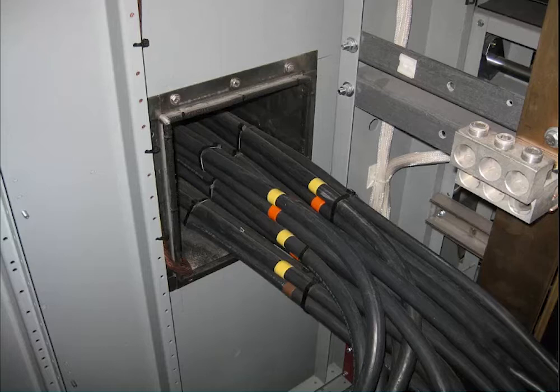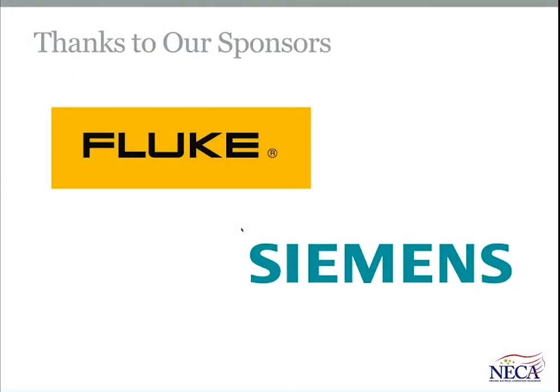And as soon as you start disrupting the group and the canceling effects of grouping, you start ending up with additive current that can overload any single conductors in a parallel arrangement. So that's what prompted the favorable reaction by Panel 8 to the grouping requirement for parallel conductors in wireways and auxiliary gutters. A little more planning involved if you're installing those types of arrangements. Okay, and that's the end of part 1.